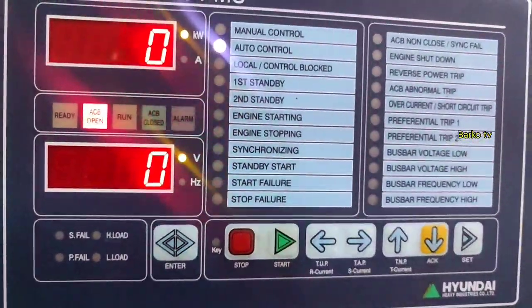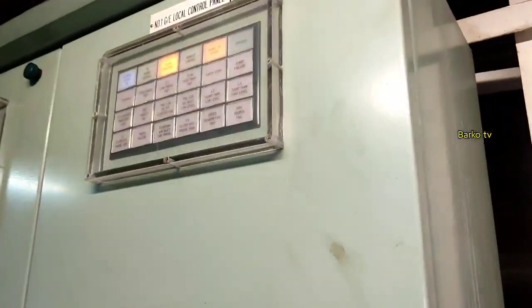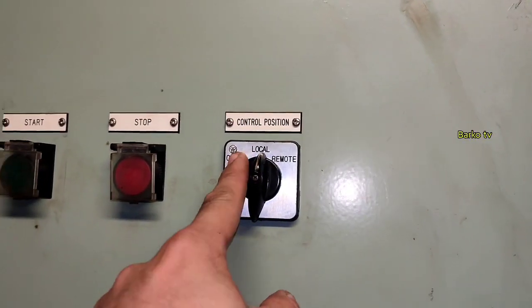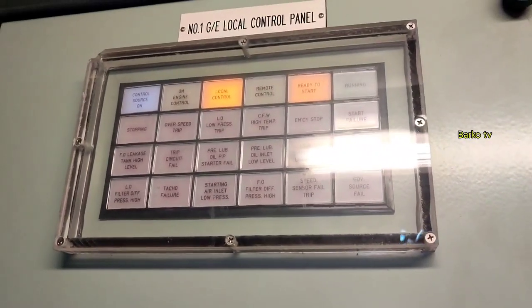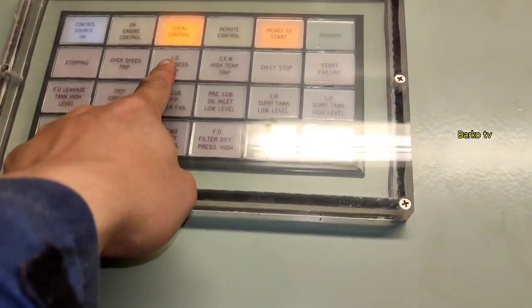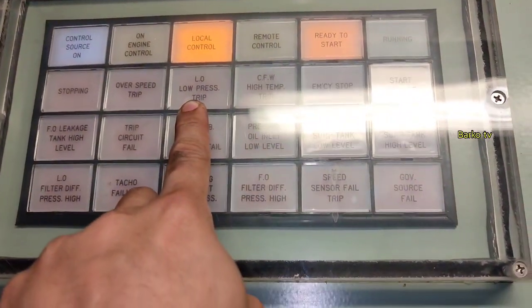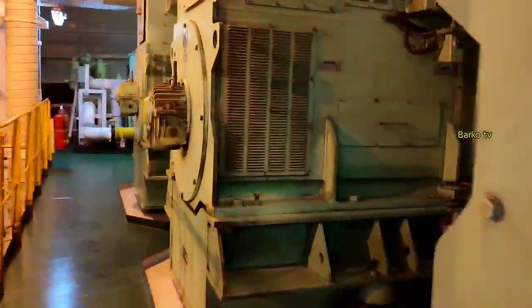We go to the local panel. This is very important — at the local panel, shift to local to isolate. By the way, the alarm is 'low pressure trip'. That is the alarm during starting.